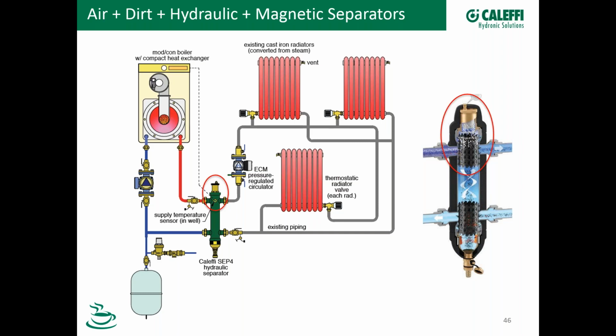So now look what you're doing there: you're turning that boiler and that separator into a miniature buffer tank for your system. So in addition to the fluid volume in the boiler, let's say that boiler holds 2 gallons of water, my separator may have 1.82 gallons of water in there, plus all the piping. So now that entire circuit from the boiler through the separator back up to the boiler is additional fluid capacity for a miniature buffer.